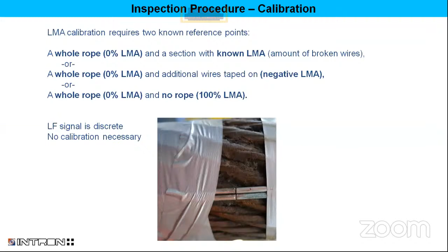The LF signal is actually discrete, so it doesn't require any calibration, but with our equipment, it will make data analysis a lot easier if you set the thresholds at what point it should consider a broken wire.